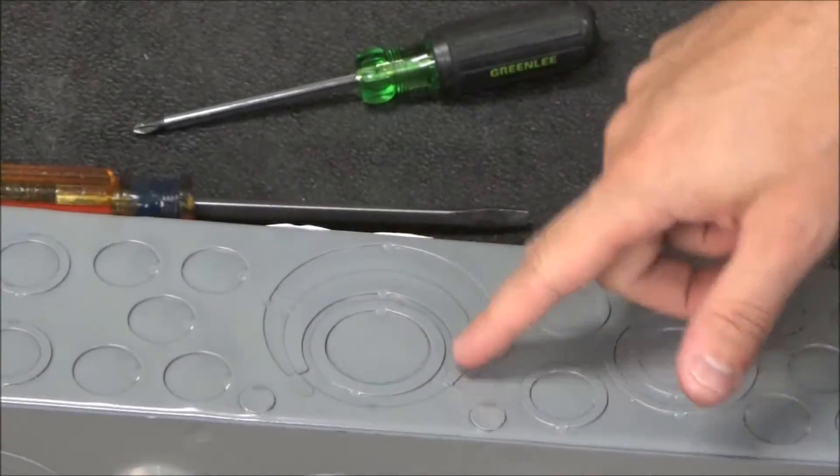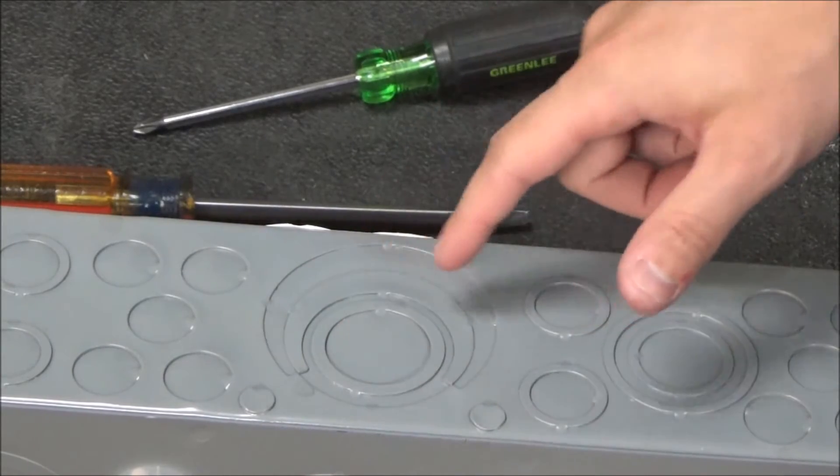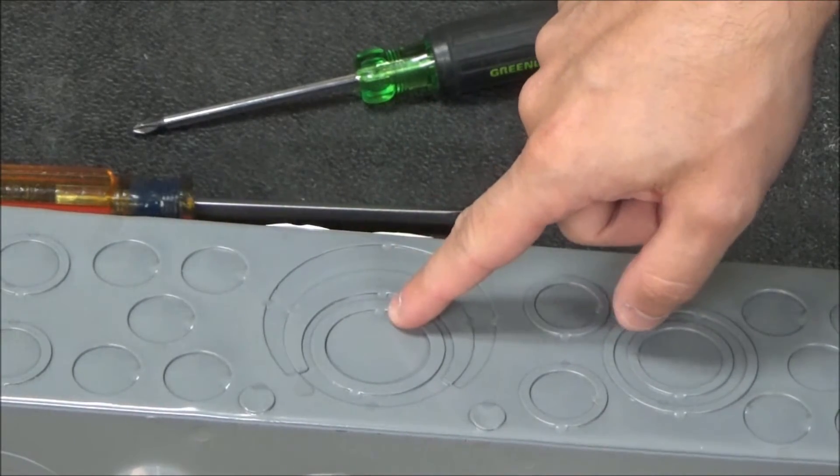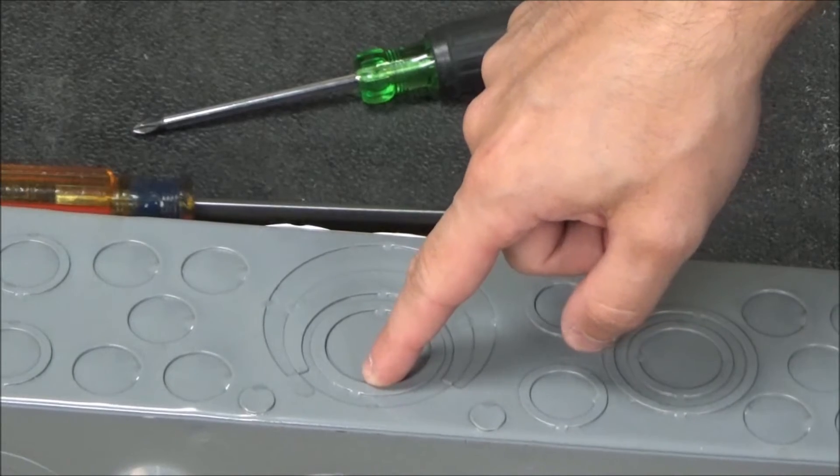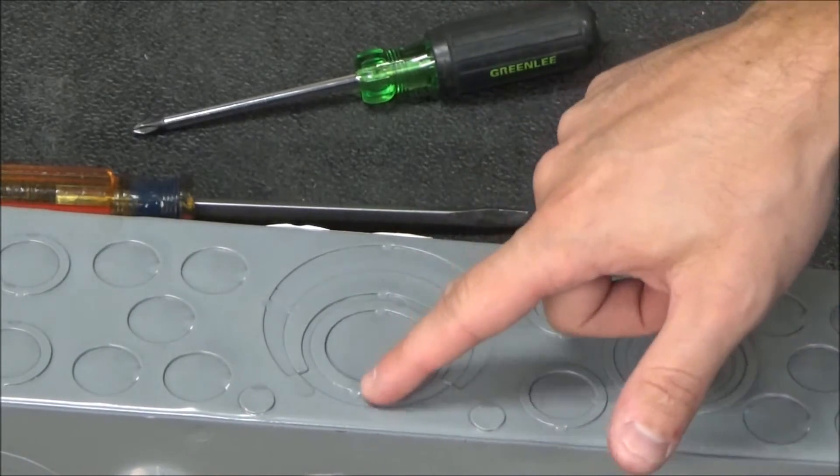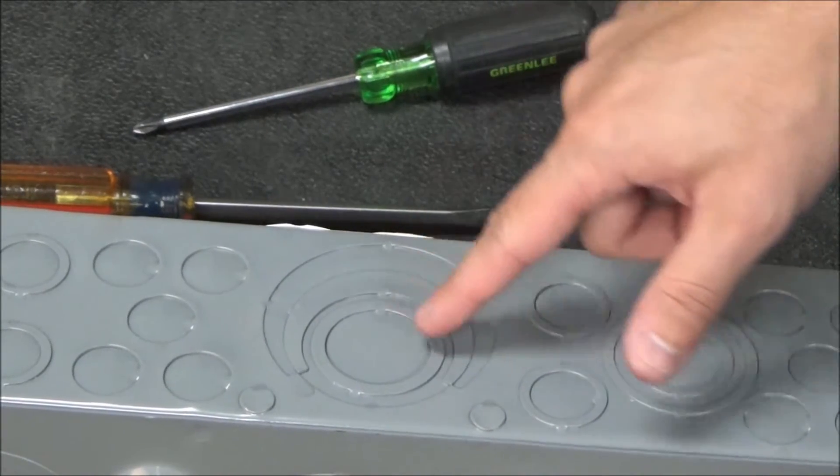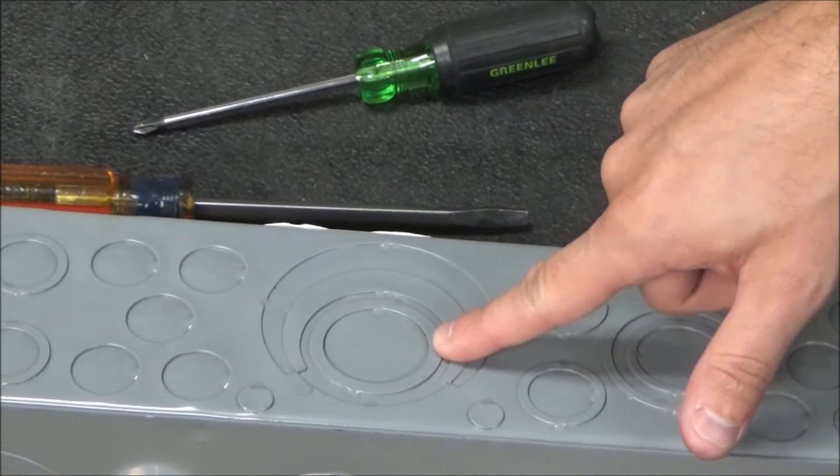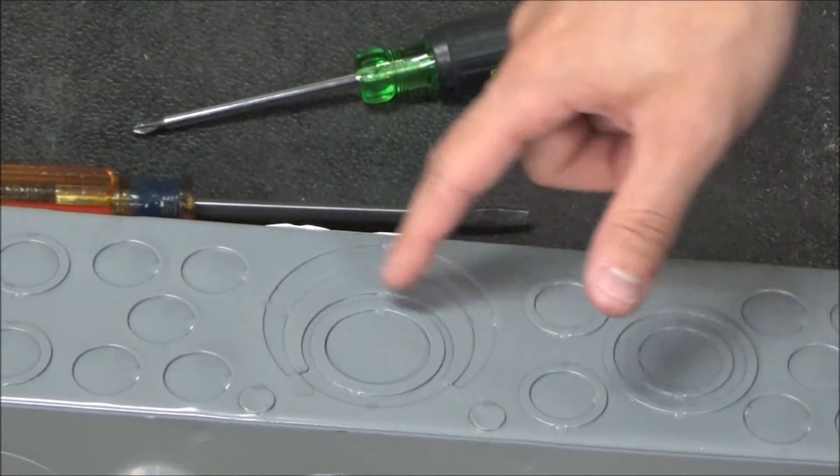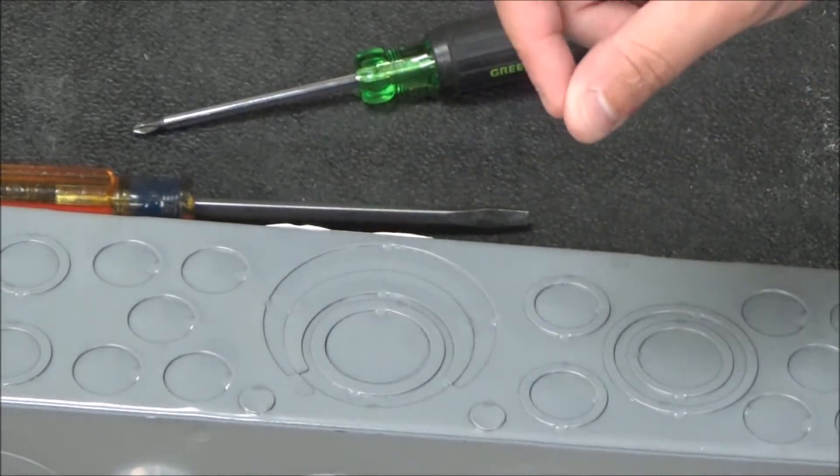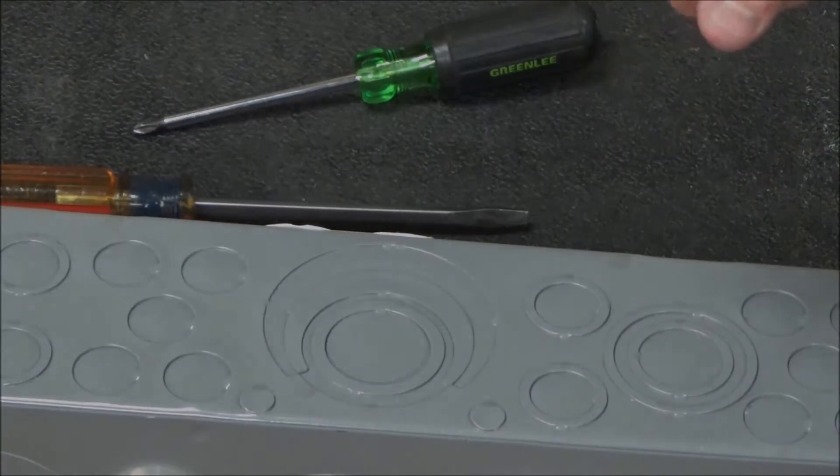You'll notice that the knockouts have spot welds which connect them to the load center. This one has one, so you go to the opposite and that's where you'll knock it out. This one has two, so you'll go in the middle to knock it out. And if it has three, you just find your way in between them and that's how you'll knock it out and remove it.